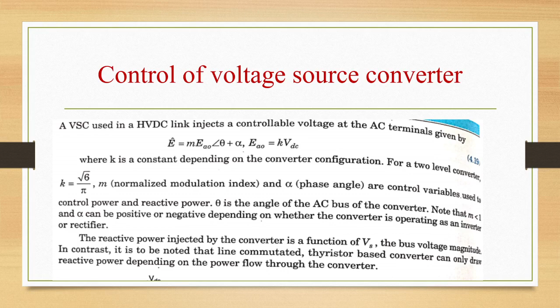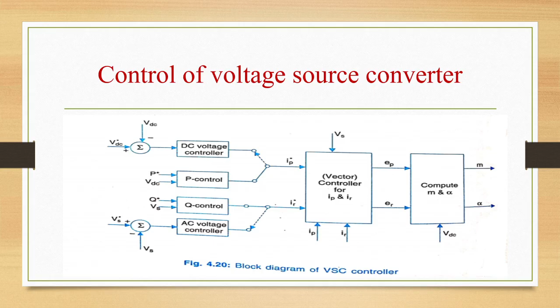So the block diagram of the controllers for VSC is shown in the figure. Here IP and IR are the active and reactive components of the AC current drawn by the converter. So IP is equal to P by Vs, and IR is equal to Q by Vs. Reference values for the active element IP is obtained either from the power controller or DC voltage controller. The reference value for the reactive current IR is obtained from the specified reactive power or AC voltage controller.